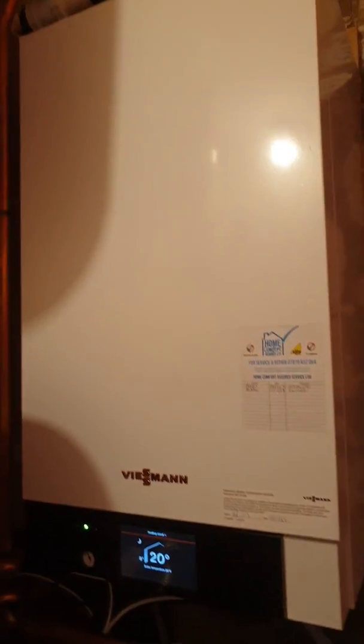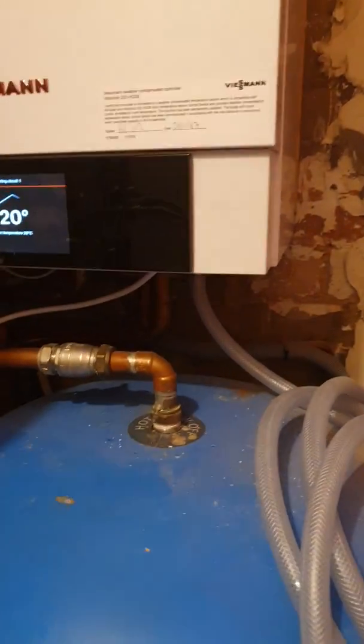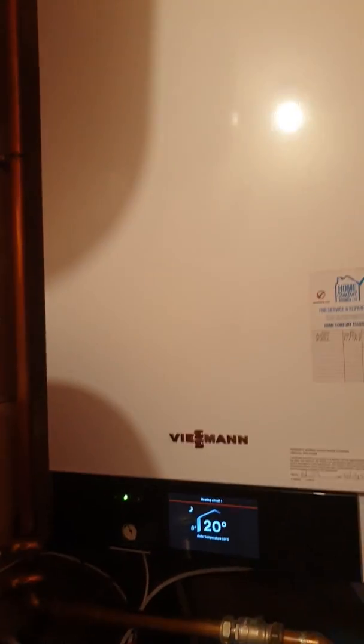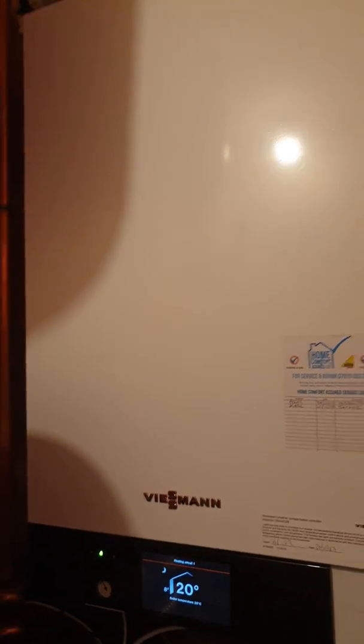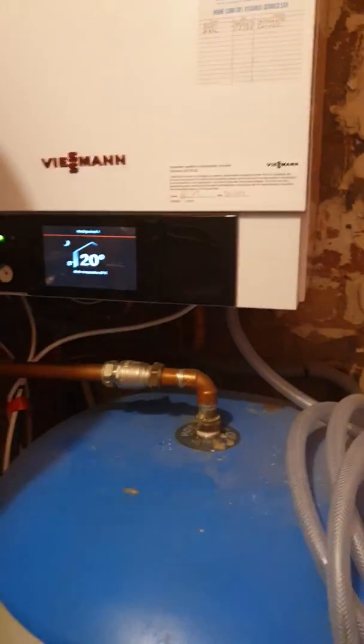I returned to a job I put in about three years ago — a Viessmann 200, as you'd expect from me. This was quite an interesting job, a little bit complicated. It was a poor installation, poor temperature control, customers complaining, floors not heating up, some heating up. We had to rectify all of that, and the boiler had failed — the heat exchanger had failed on it. I think it's three years old.